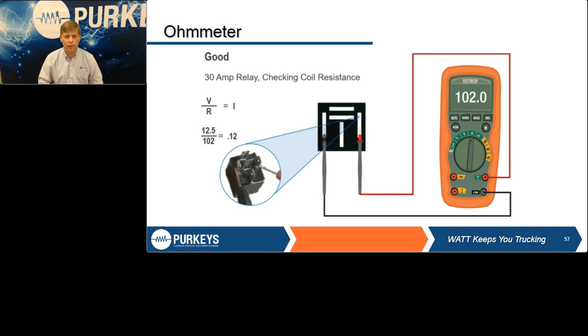And the first thing we would check would be the coil. So you're going to take your meter leads, go on the two outside ones, make sure you're on ohms, and we're going to see what the resistance of that coil is.